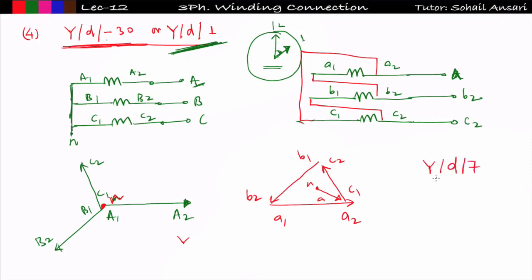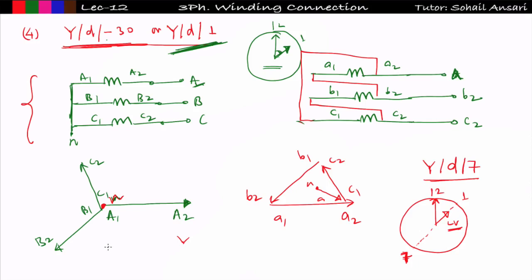Now I have to make YD7. In YD1, the HV side is fixed at 12 and the LV side is at 1. YD7 is just opposite to YD1 — I need to rotate this LV winding by 180 degrees to get YD7. So I will leave the primary winding phasor diagram the same as in YD1, but change the orientation of the LV winding by 180 degrees to shift it from position 1 to position 7.